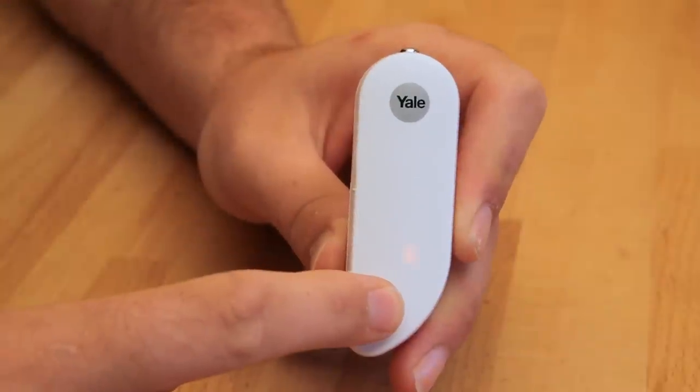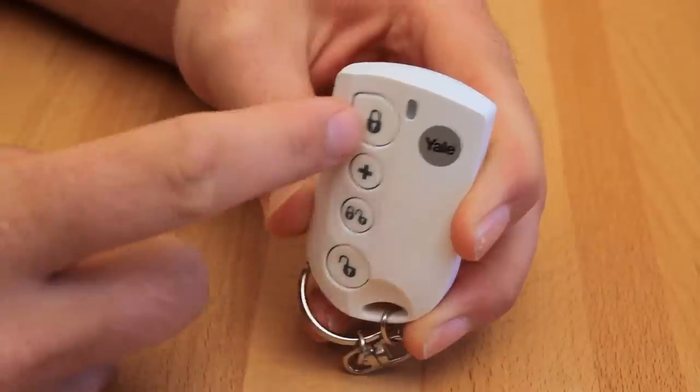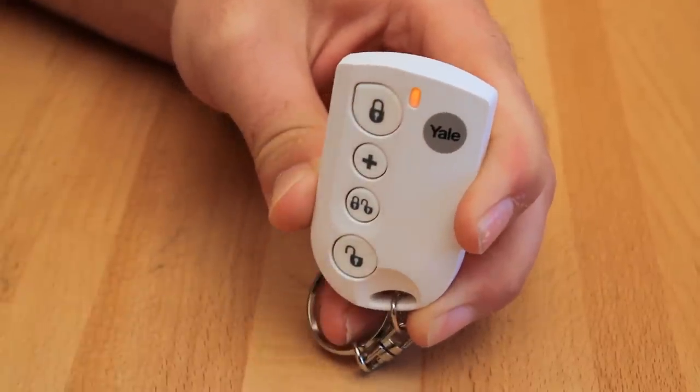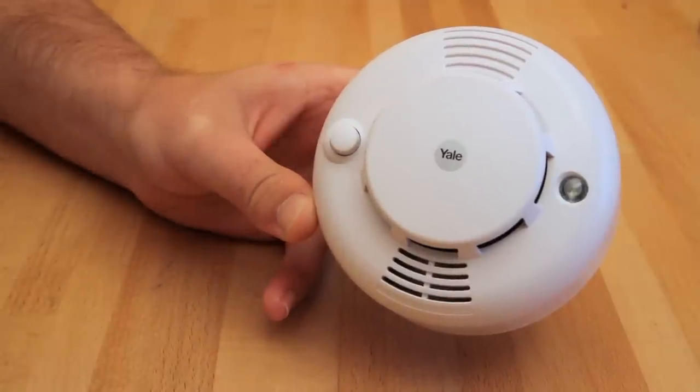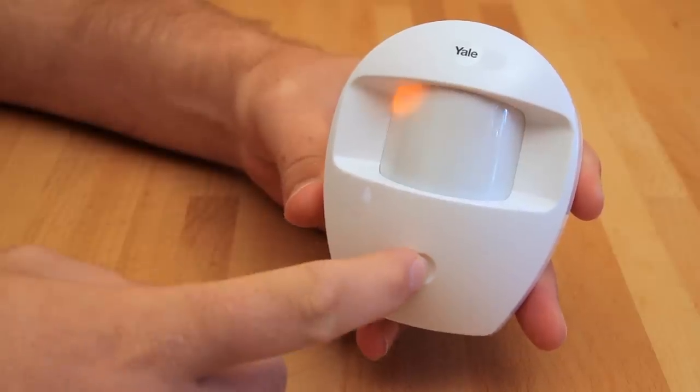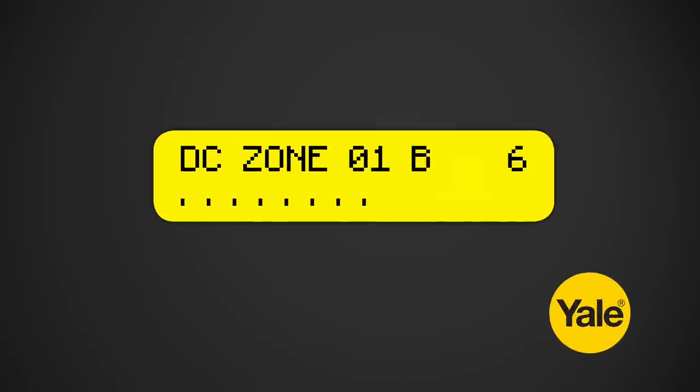Before proceeding to mount the components, physically check the control panel will receive the system radio transmissions. To do this, hold the components in the desired mounting locations and one by one press the test button on each component. If the sensor signal reached the control panel, the screen will briefly display a message like this.